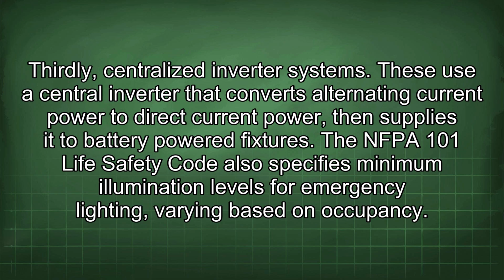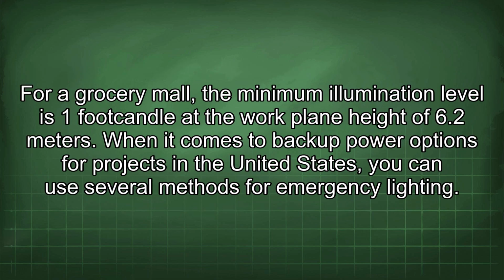The NFPA 101 Life Safety Code also specifies minimum illumination levels for emergency lighting, varying based on occupancy. For a grocery mall, the minimum illumination level is 1 foot candle at the work plane height of 6.2 meters. When it comes to backup power options for projects in the United States, you can use several methods for emergency lighting.